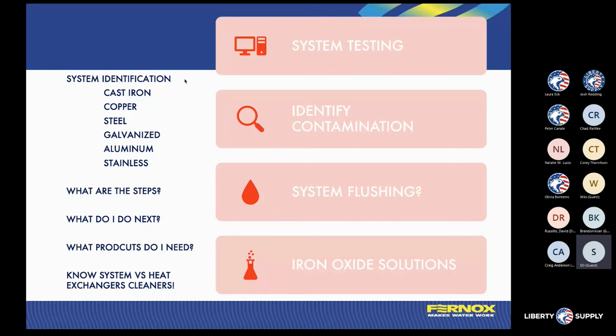Iron oxide is a particular problem that is going to become more resident as we get into the different types of technologies that we're going to, such as ECM pumps. ECM pumps, because we're going from a copper wound motor to a permanent magnet solution. If we don't have a device that's going to absorb or remove that iron oxide from that system, because that new ECM circulator has a permanent magnet inside of it, that iron oxide is going to be naturally attracted to that circulator. Most circulators, depending on their size, are either water and system lubricated and cooled through the system water that's coming by it, or if you're in a commercial application, a lot of times that seal will get built up because you have iron oxide, and that's going to lead to a premature seal leak. So either way, are issues when we leave that iron oxide solution into our systems.